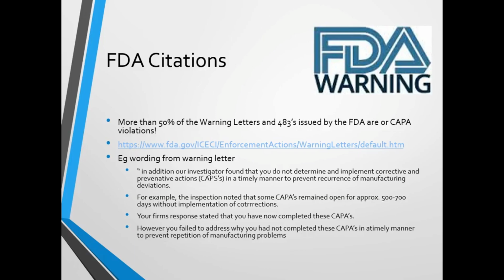In addition, our investigator found that you do not determine and implement corrective and preventative actions in a timely manner to prevent recurrence of manufacturing deviations. For example, the inspection noted that some CAPAs remained open for approximately 500 to 700 days without implementation of corrections. Your firm's response stated that you have now completed these CAPAs. However, you failed to address why you had not completed these CAPAs in a timely manner to prevent repetition of manufacturing problems. So close out of your actions is very, very important as part of your CAPAs.